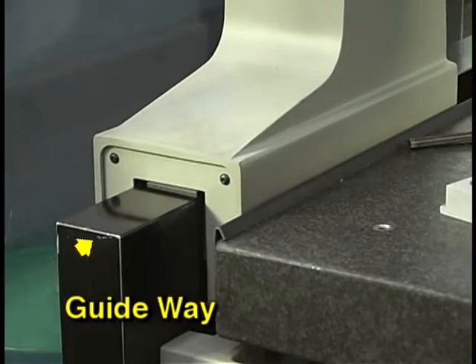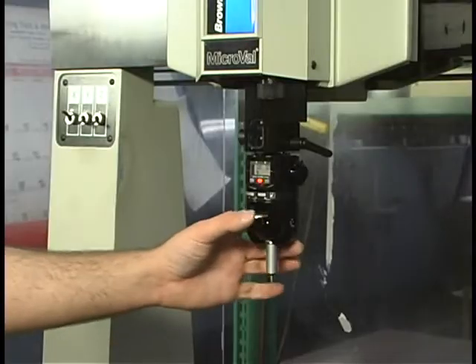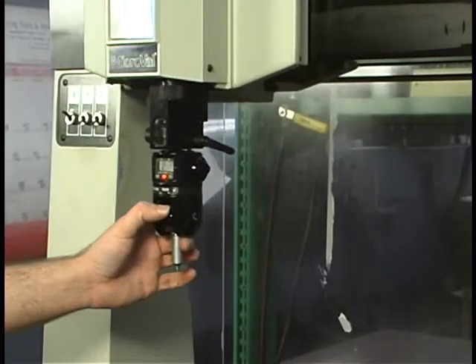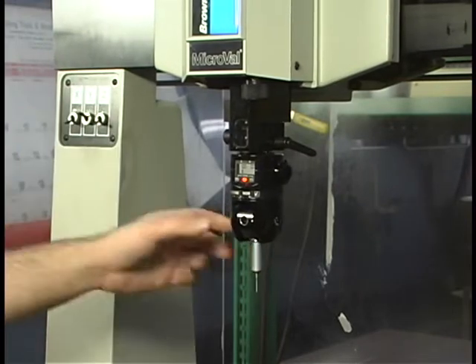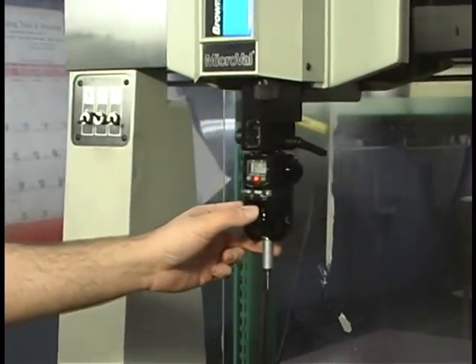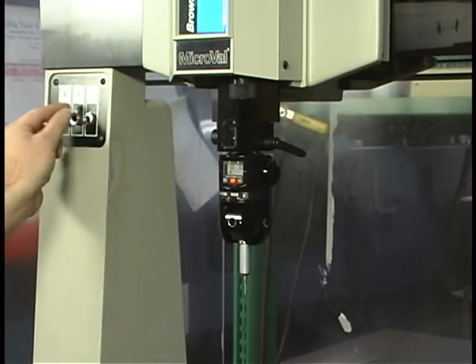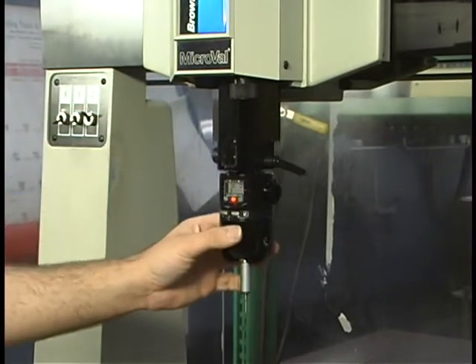All axes of movement are on guideways. On this CMM, the probe column and bridge do not actually touch the guideways during normal movement. An air compressor supplies filtered air to allow the moving surfaces to ride on a layer of pressurized air. This is called an air bearing.